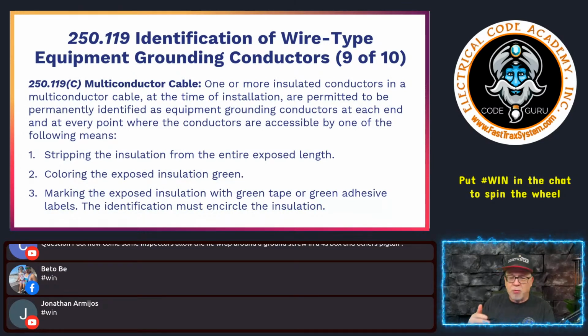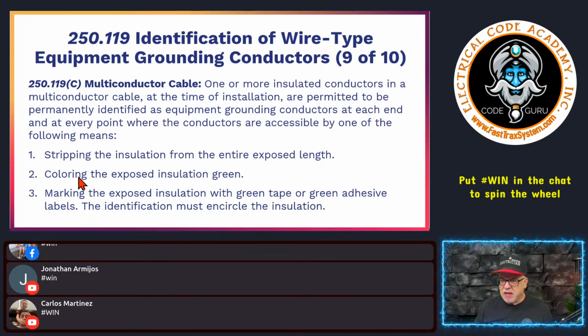A lot of people say, what does it matter? It's metal to metal. You never want to use a mounting screw that happened to be conveniently there to also be where you make your bond connection. You don't want to do that. You want a dedicated screw or dedicated connection, whether it's those little clips that clip onto the metal boxes or whatnot. You want it to be dedicated to the equipment ground. You don't want to use any mounting screws, any mounting holes that were not designed for use with the equipment ground. Okay, you get me?